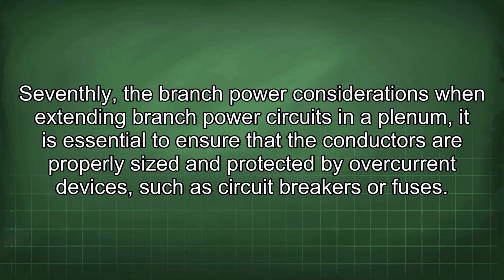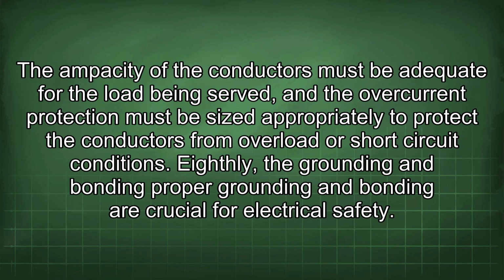Seventhly, the branch power considerations. When extending branch power circuits in a plenum, it is essential to ensure that the conductors are properly sized and protected by overcurrent devices such as circuit breakers or fuses. The ampacity of the conductors must be adequate for the load being served, and the overcurrent protection must be sized appropriately to protect the conductors from overload or short-circuit conditions.